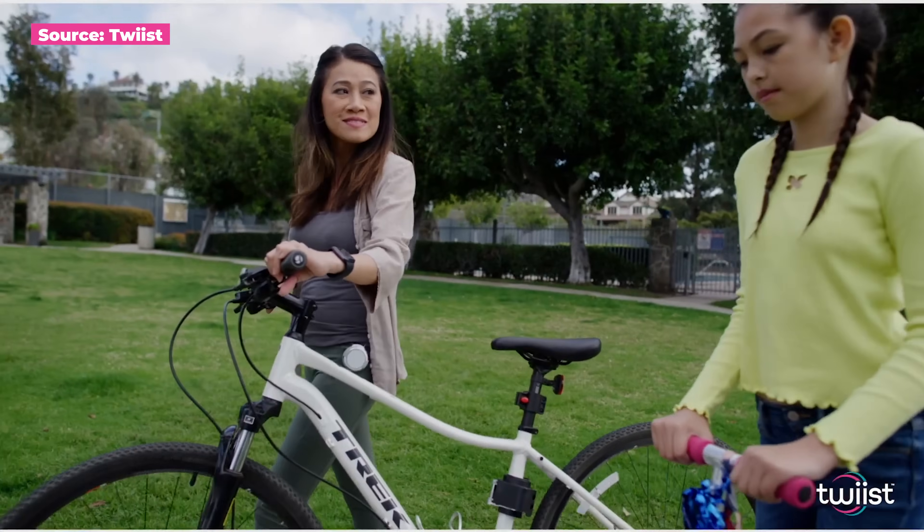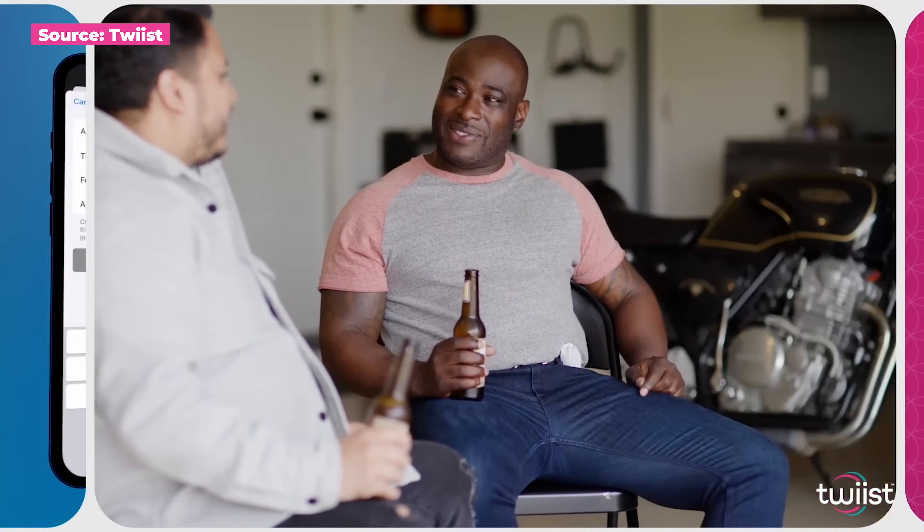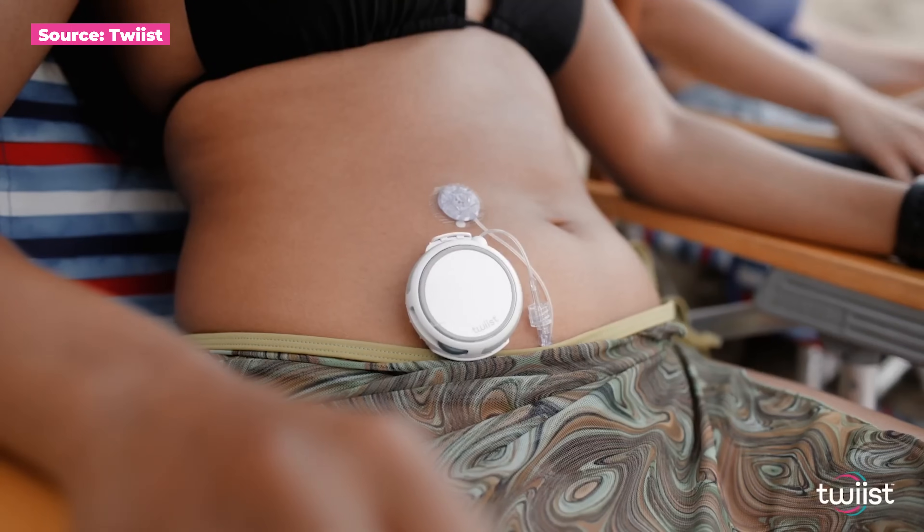To your point about how the CGM speaks directly to the pump — what I really like about that is as someone who uses open source apps, the one thing missing is I can't leave my phone in the other room. I've been experimenting with other systems that have that direct connection like Twiist, and it's given me a sense of freedom back. I'm happy to hear that's how you've integrated them. What about the adhesive? Last time we spoke, you mentioned there are a few ways to wear this — you can clip it, pocket it, or use an adhesive. I was told that at launch the adhesive won't be there. What's going on with that?